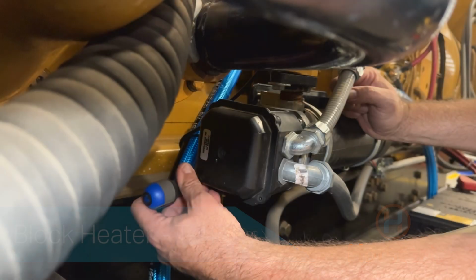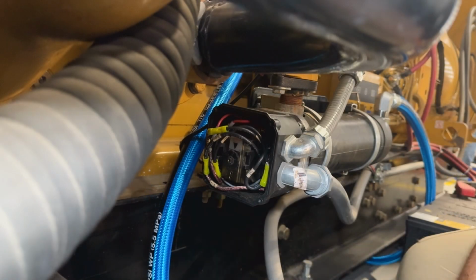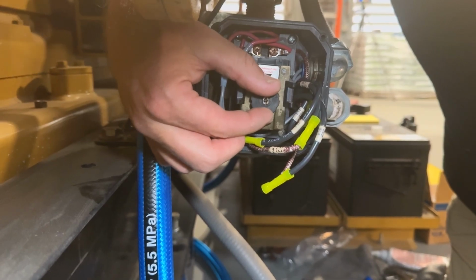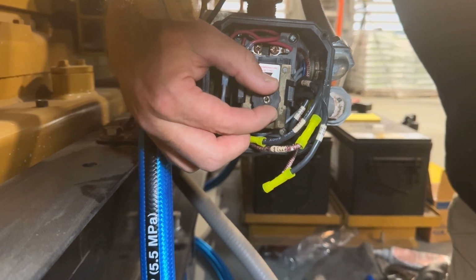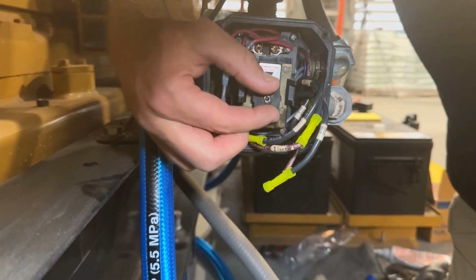Block heaters typically have an adjustable or fixed thermostat to control heater operation. If the existing heater has an adjustable thermostat, lower the set point to 95 degrees Fahrenheit. If the heater has a fixed thermostat, contact Hotstart for additional support.